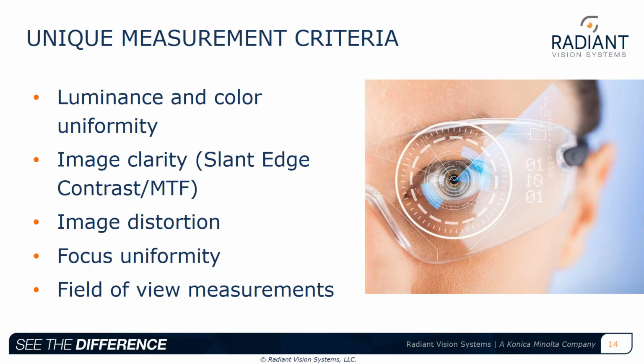to characterize. And then also, one of the main specifications that manufacturers list for these devices is the field of view. And the field of view can be a little bit of a subjective specification. It can be dependent on the exit pupil of the device, the observer, the entrance pupil of the observer. And so the specification may say one thing, but it might be very interesting to actually verify what the true field of view of the device is.